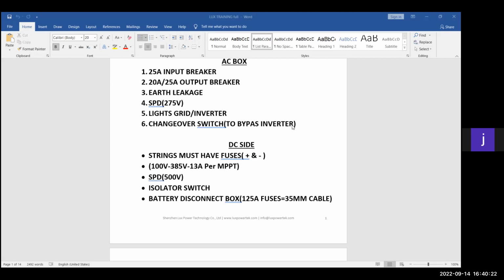Now on the DC side, this is very, very important. A lot of my warranty claims come from the DC side of my inverters. We have a lot of installers that work with live DC wires. I can't stretch out this training more on this side, but very important on the DC side, don't work with live DC wires. We have a lot of installers that touch the body with a live DC wire and it arcs against the body and you damage my inverters. Nine out of 10 times, if you arc your PV panels against my body, you blow my main board.